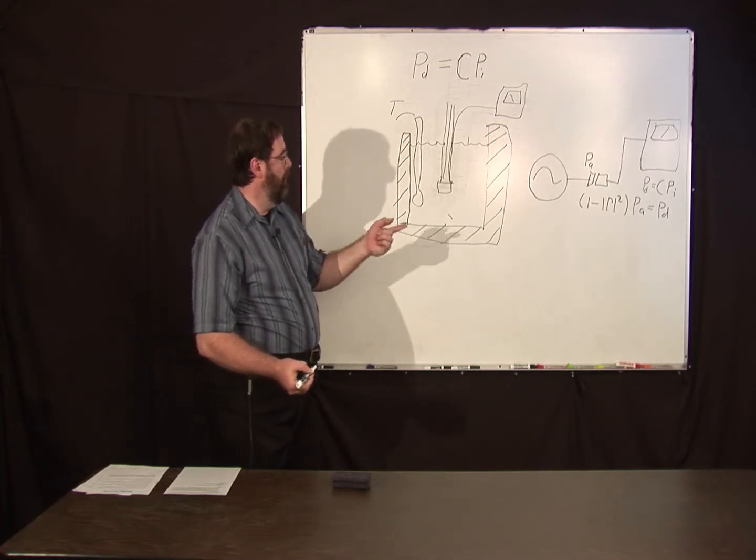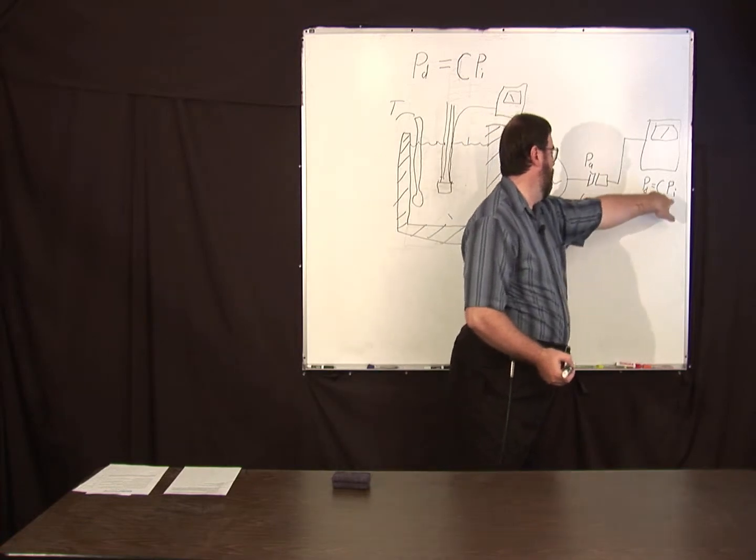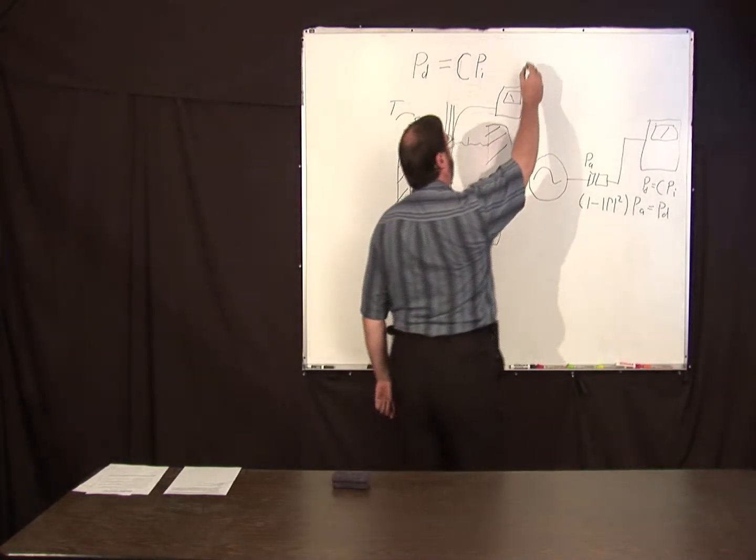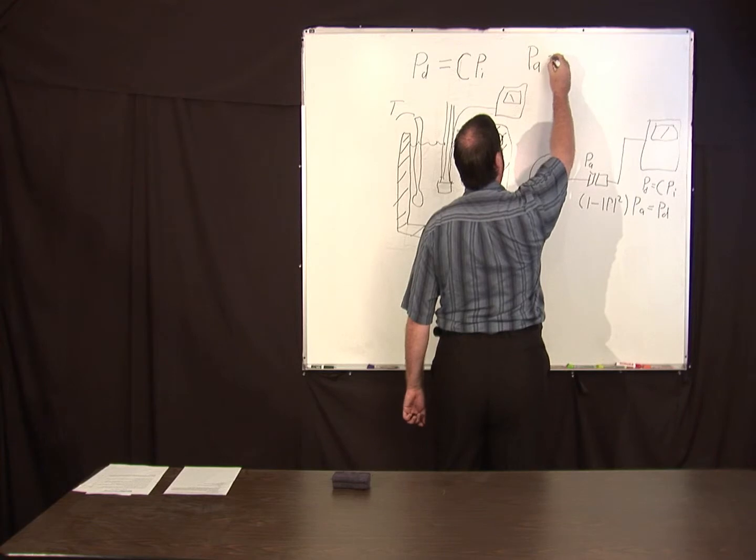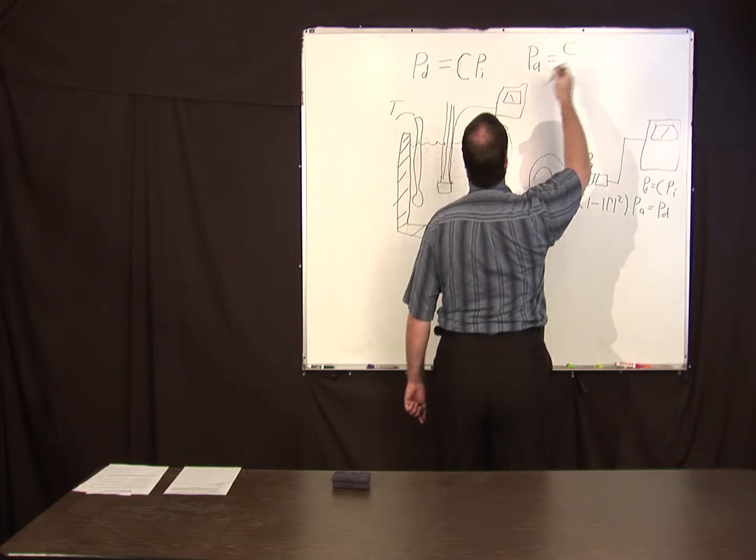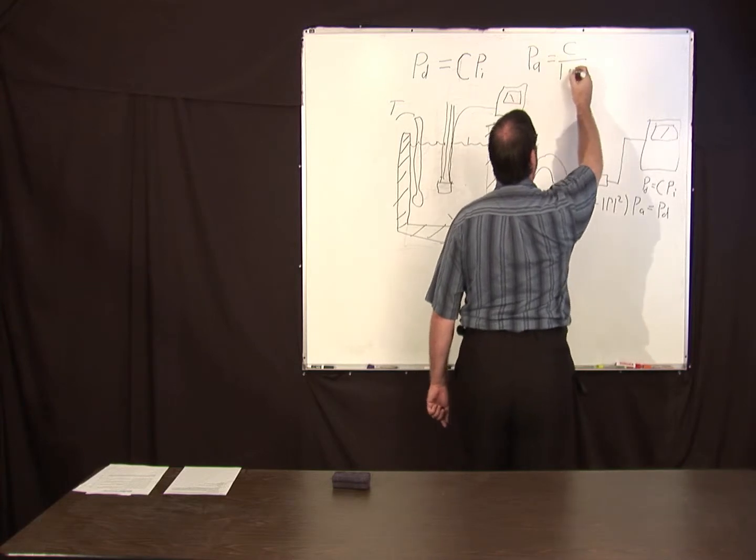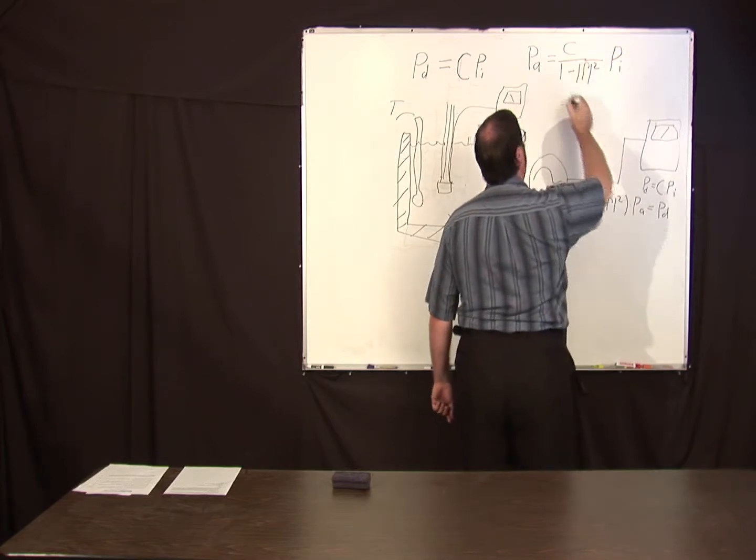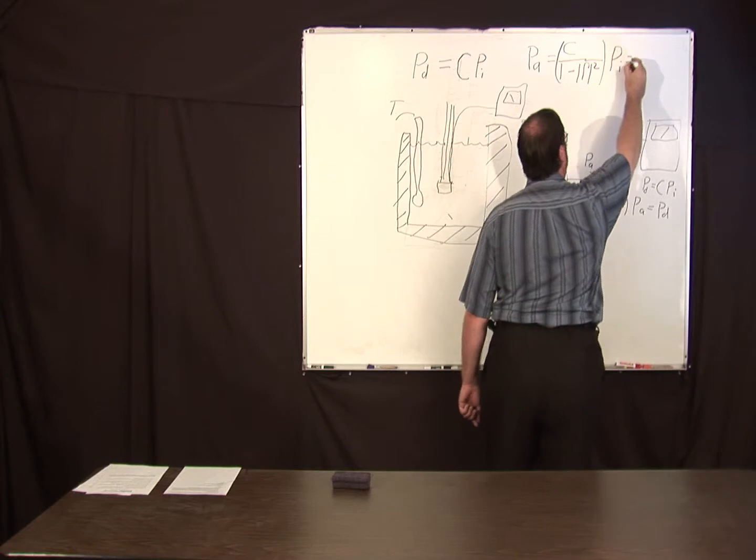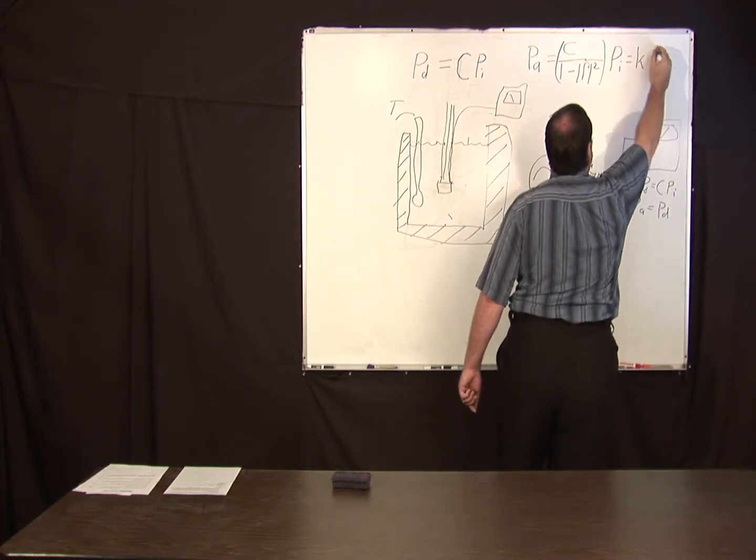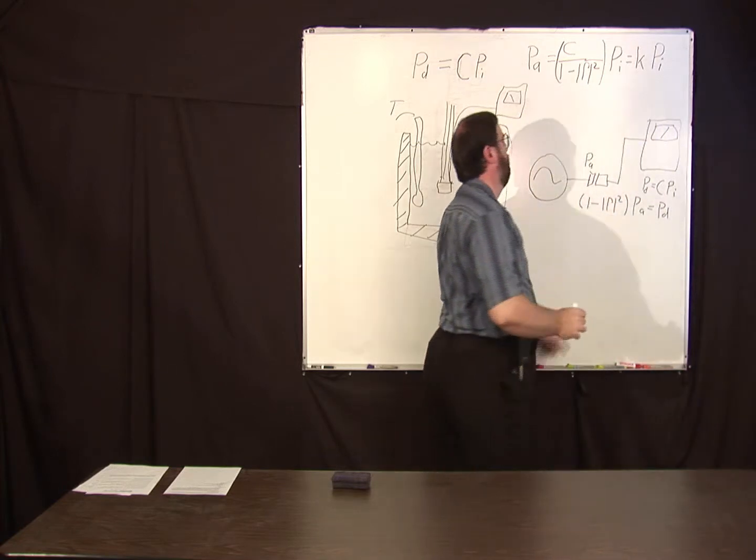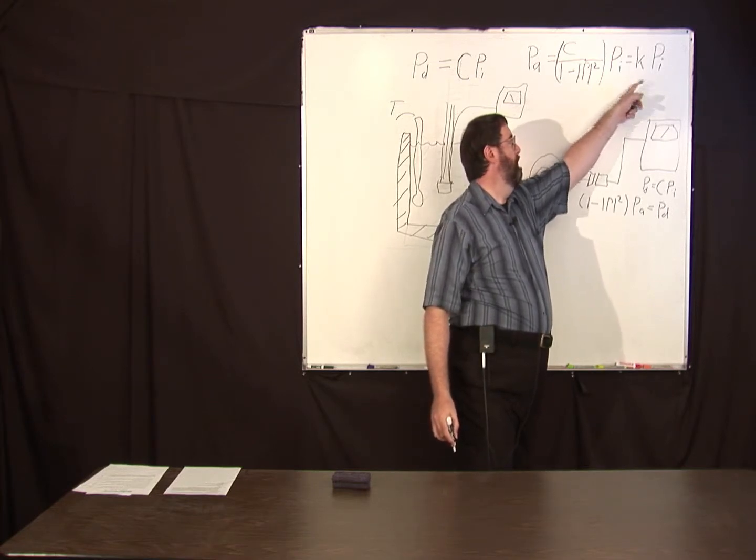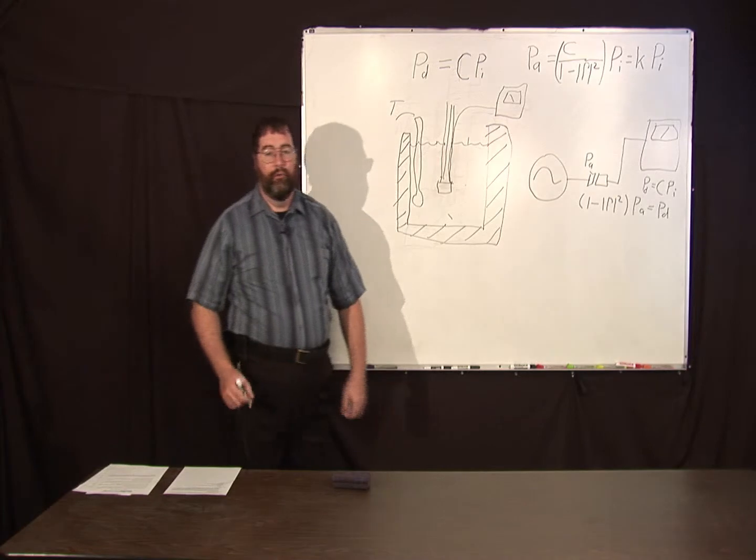So how do you do that? There is this correction. The power actually delivered to the power sensor is going to be 1 minus gamma reflection coefficient squared times the available power. That's equal to the power delivered. So if you put that in there, we come to the conclusion that the available power equals this constant we got from calorimetry, divided by 1 minus the reflection coefficient squared times the indicated power. This thing here, we'll just call that K. This K is basically related to the calibration factor that you'll see on most power sensors.